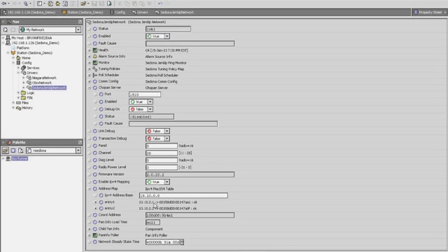Device 10.10.0.1, which is mapped to from the IPv6 address of the Sedona controller. This area of the property sheet is very important when you're trying to troubleshoot your RF network, as this is indicative of what is taking place on the wireless side of things. So if you have devices that seem to be giving you communication problems, you can verify that they're actually on the network in this screen.